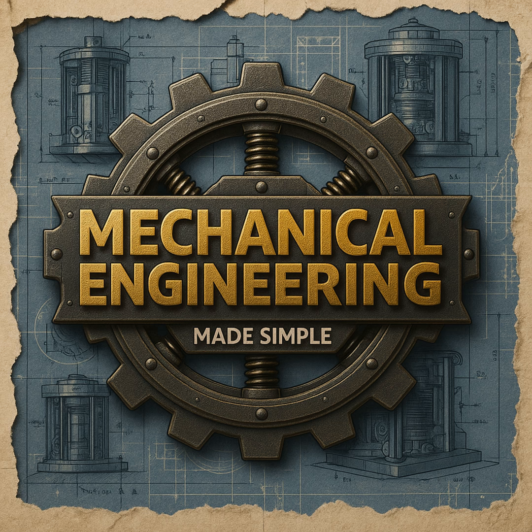Okay, that covers the rotaries. Now let's shift to the powerhouse, the machine that really dominated for decades in terms of sheer volume, the centrifugal compressor. Yeah, if you measure by capacity CFM, or just total installed horsepower, centrifugals are king. These are dynamic machines, totally different from positive displacement. Dynamic meaning they use high-speed rotating impellers to fling the air outwards, adding velocity, and then a diffuser section converts that velocity into pressure. They're designed for huge flows, think 1,000 up to maybe 30,000 CFM or even more.